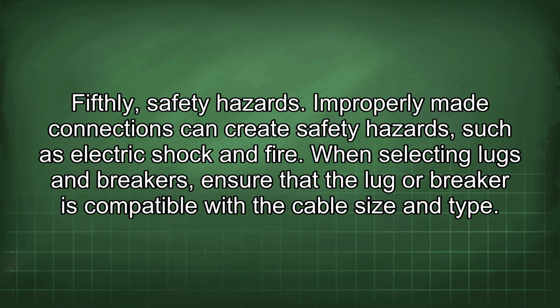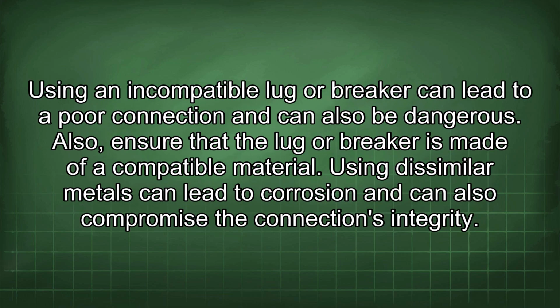When selecting lugs and breakers, ensure that the lug or breaker is compatible with the cable size and type. Using an incompatible lug or breaker can lead to a poor connection and can also be dangerous. Also, ensure that the lug or breaker is made of a compatible material. Using dissimilar metals can lead to corrosion and can also compromise the connection's integrity.